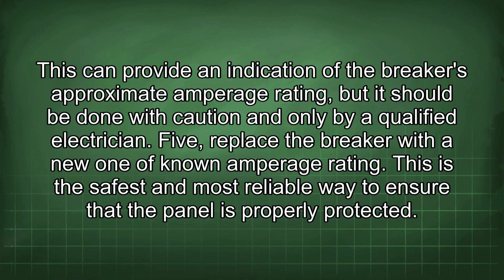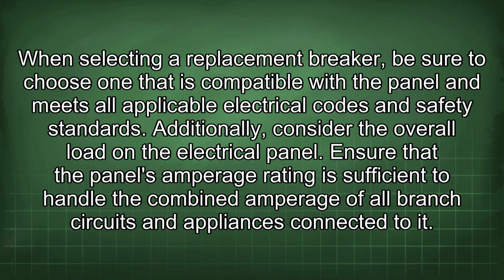5. Replace the breaker with a new one of known amperage rating. This is the safest and most reliable way to ensure that the panel is properly protected. When selecting a replacement breaker, be sure to choose one that is compatible with the panel and meets all applicable electrical codes and safety standards. Additionally, consider the overall load on the electrical panel.